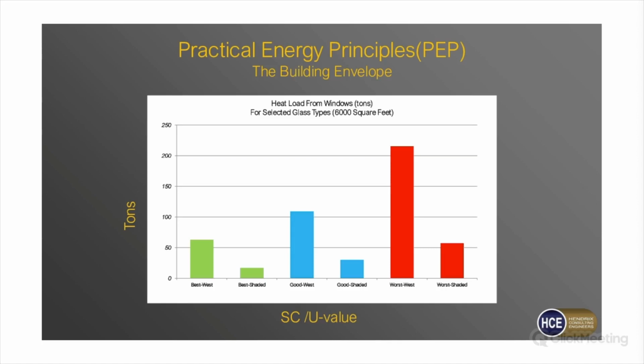Each pair represents the same square footage of glass under different conditions. With our best glass facing west, we're looking at about 60 tons; if that same glass is shaded, we're down closer to 20 or 25 tons, so shading makes a huge difference in how the glass performs. Good glass isn't quite as good as the best. And with the worst glass, really bad single pane glass that energy codes try to keep you from using, you can easily triple or quadruple the loads you get from your glass.